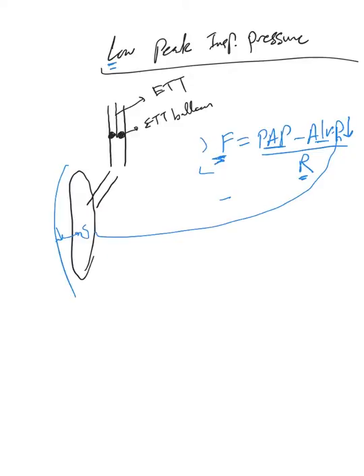Which means we use it in volume control - the proximal airway pressure has to maintain this flow. So it will decrease the proximal airway pressure to keep the flow, and that will lead to low peak inspiratory pressure. That's one explanation. The second explanation...